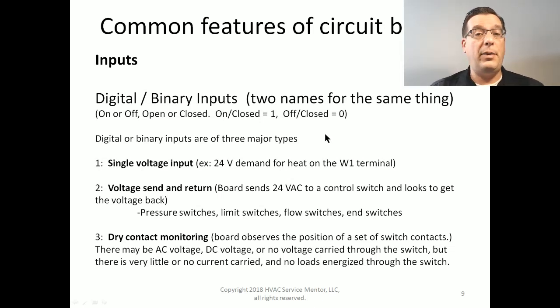In the digital or binary type of input, there are three major types. The first type is probably the most common. It's called a single voltage input. A single voltage input could be the 24 volt demand for heat on the W1 terminal of your furnace control board. That's your call for heat. For cooling, that would be 24 volts on the Y terminal. Okay, that's a single voltage input.